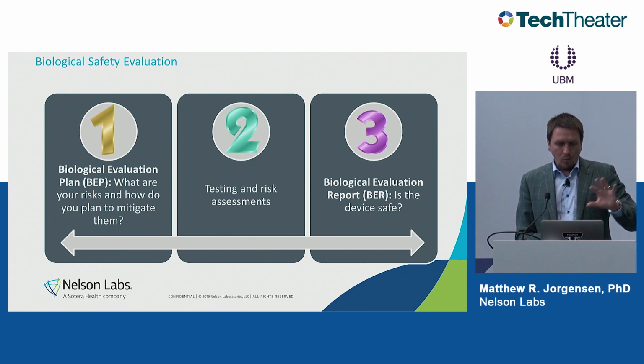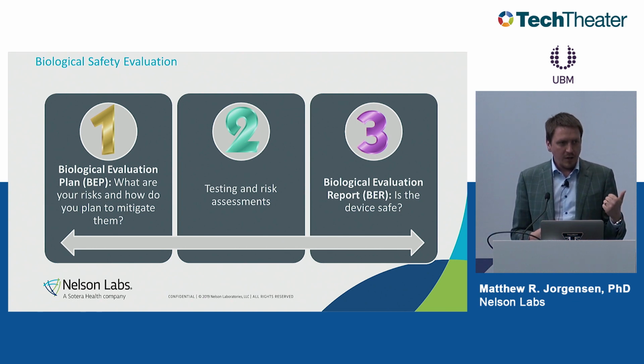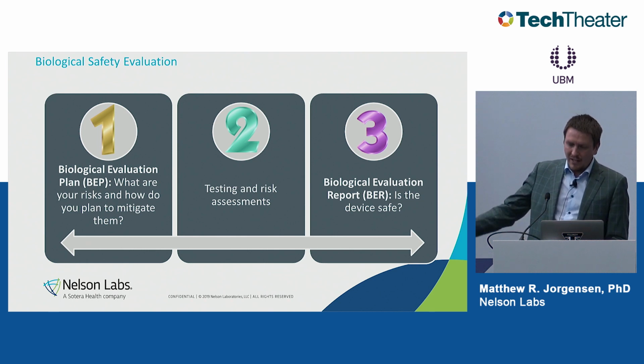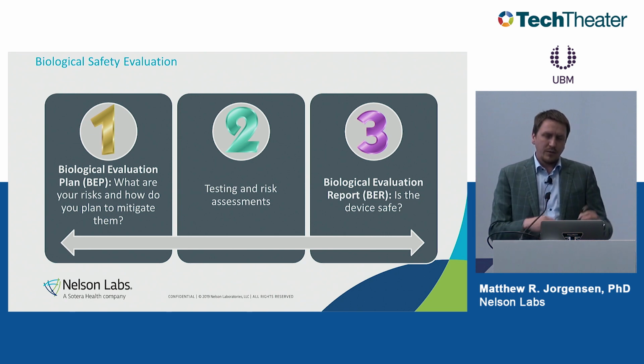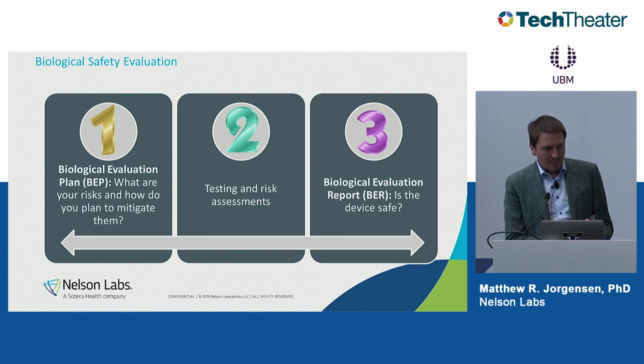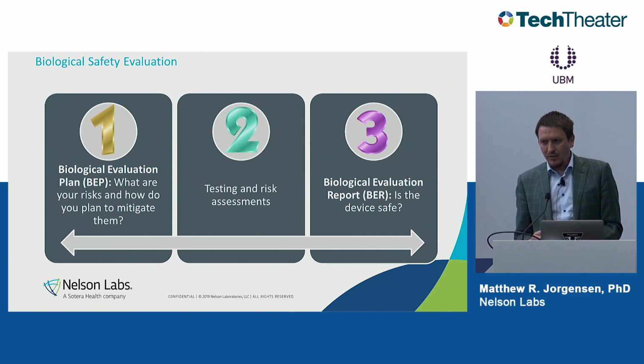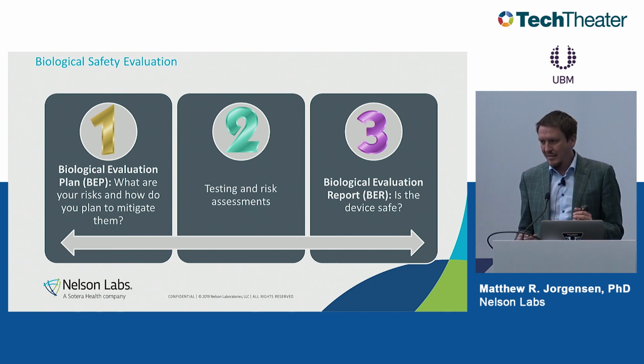And then, once you have the plan and you've established what you're going to do to address these risks, then you go through the process of addressing those risks, either through written evaluations or testing if necessary. Then finally, you have a summary report where you explain to the regulatory body, here's our device, these are the risks that were identified, here's what we did to mitigate those risks, and in conclusion, since everything passed and the evaluations are favorable, the device is safe.